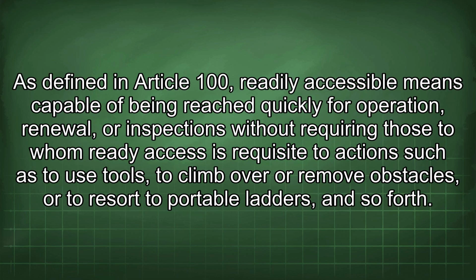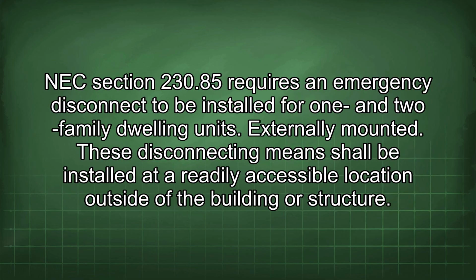As defined in Article 100, readily accessible means capable of being reached quickly for operation, renewal, or inspections without requiring those to whom ready access is requisite to actions such as to use tools, to climb over or remove obstacles, or to resort to portable ladders, and so forth. NEC Section 230.85 requires an emergency disconnect to be installed for 1 and 2 family dwelling units, externally mounted. These disconnecting means shall be installed at a readily accessible location outside of the building or structure.